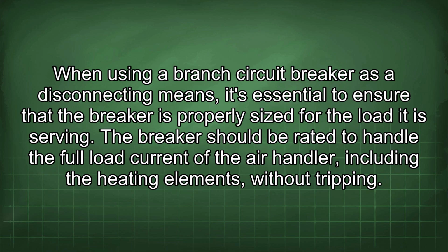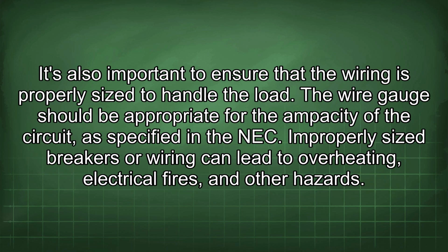The breaker should be rated to handle the full load current of the air handler, including the heating elements, without tripping. It's also important to ensure that the wiring is properly sized to handle the load. The wire gauge should be appropriate for the ampacity of the circuit, as specified in the NEC. Improperly sized breakers or wiring can lead to overheating, electrical fires, and other hazards.